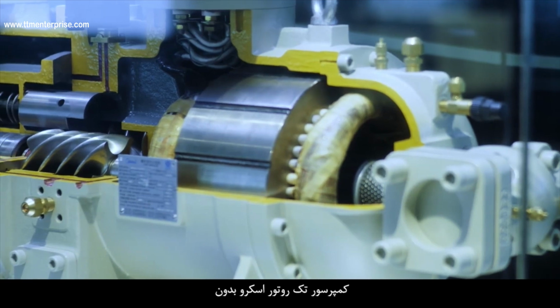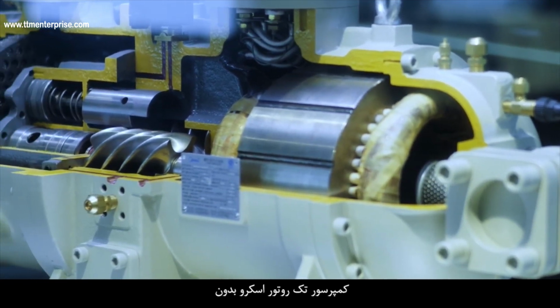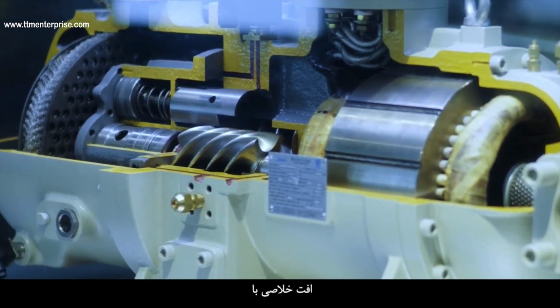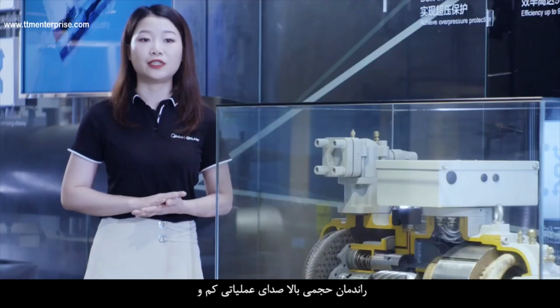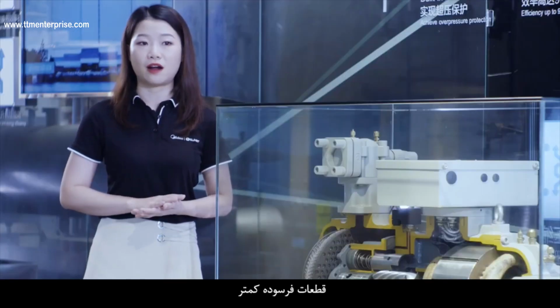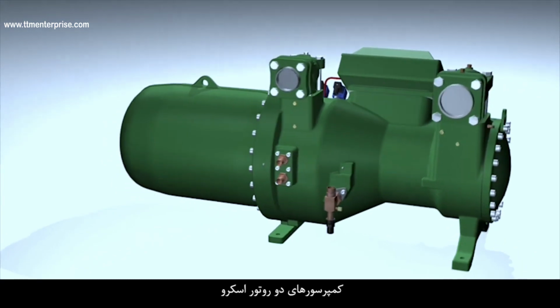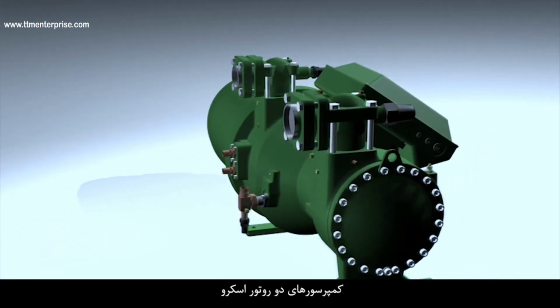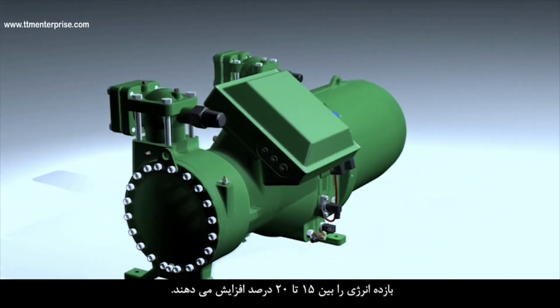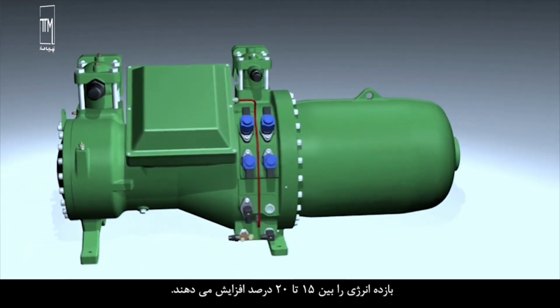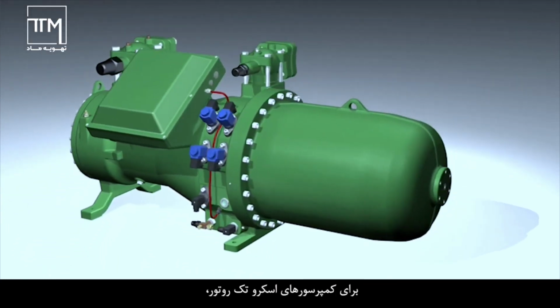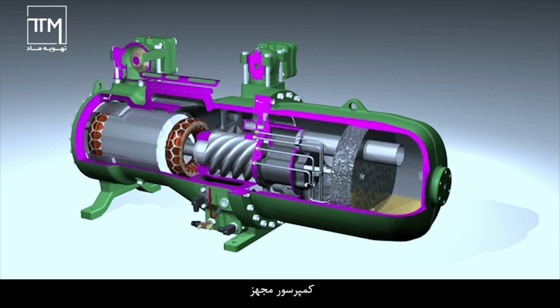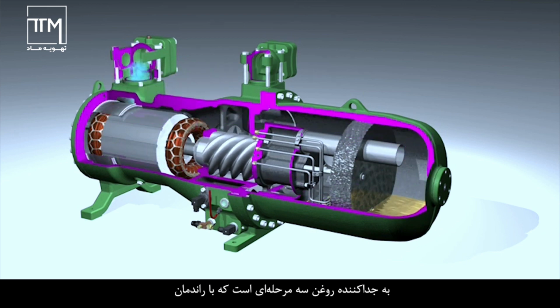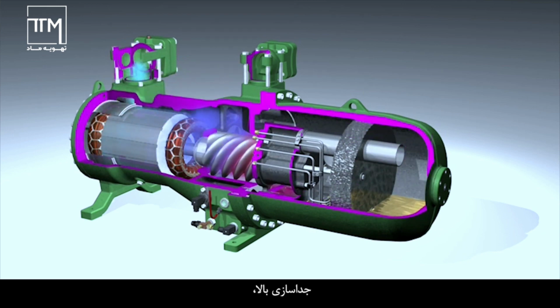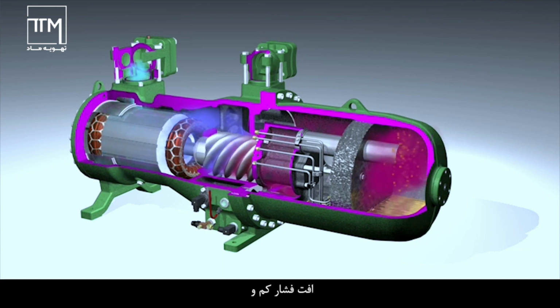Compared to the single-rotor screw compressor, it has no clearance loss, high volumetric efficiency, low operating noise, and fewer wearing parts. The twin-rotor screw compressors increase energy efficiency by 15 to 20% compared to the single-rotor screw compressors. The compressor is equipped with a 3-stage oil separator featuring high separation efficiency, small pressure drop, and a low oil throwing rate.